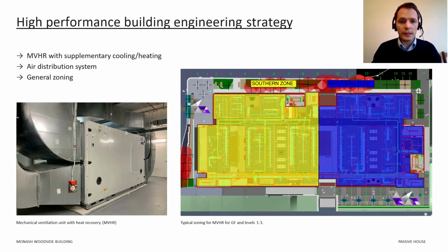Supplementary cooling and heating is applied via fan coil units assigned to the various spaces like offices, meeting rooms and collaborative spaces. The condensing units serving the fan coil units are modular variable refrigerant flow condensing units of the heat recovery type. They are located on the roof and have an installed cooling capacity of approximately 1,400 kilowatt and heating capacity of approximately 1,600 kilowatt.